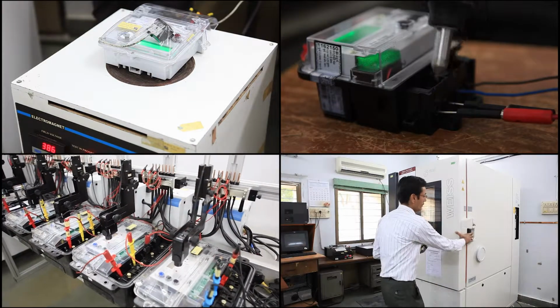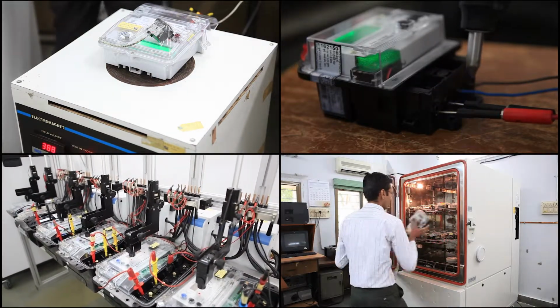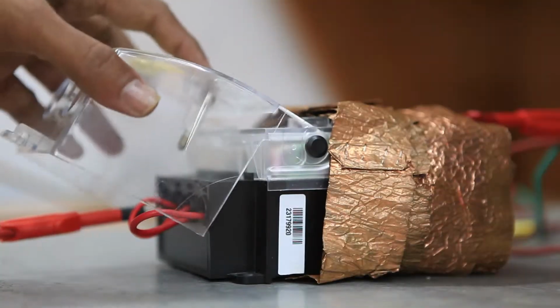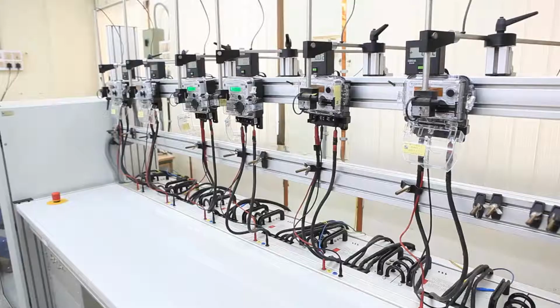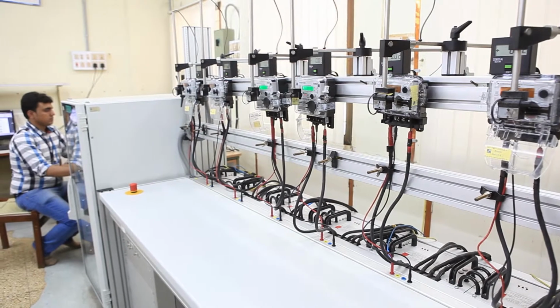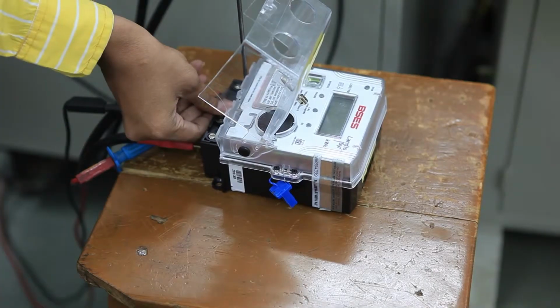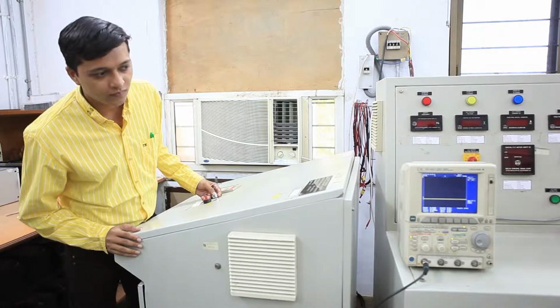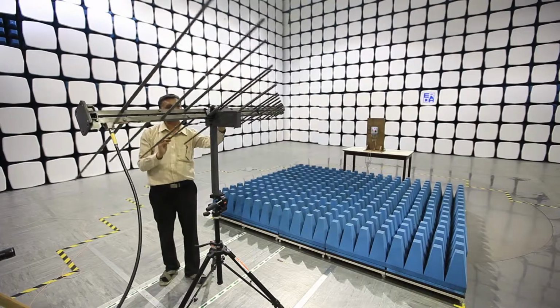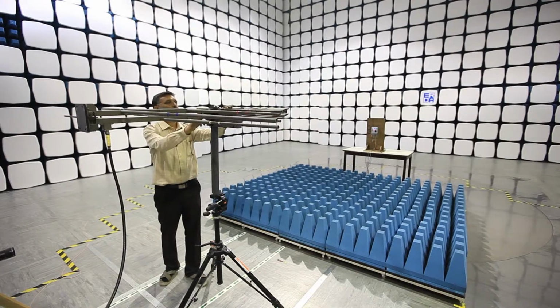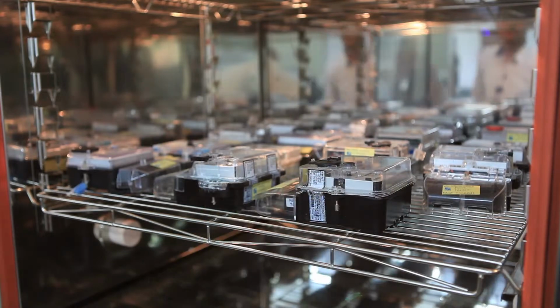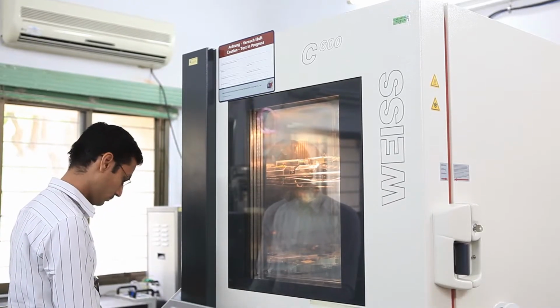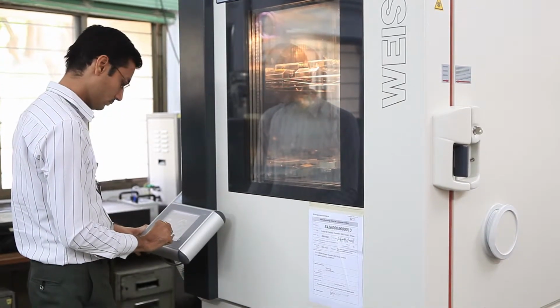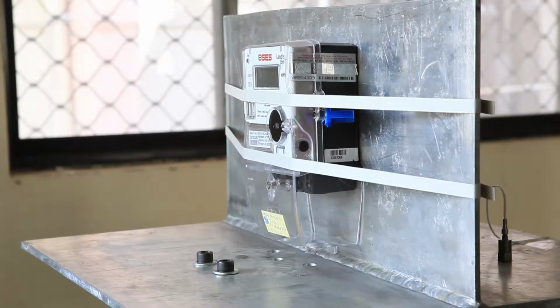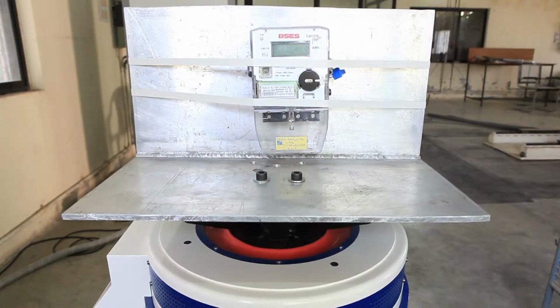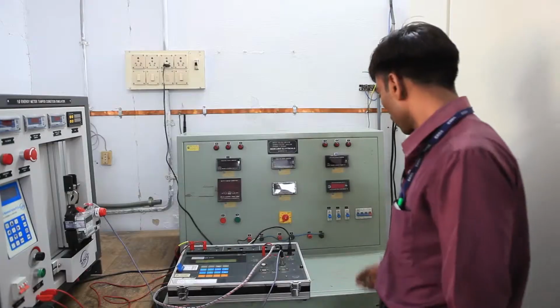ERDA has complete type test facilities for energy meters. We carry out impulse test, accuracy requirements up to 0.02 class, short time overcurrents up to 10 kiloamperes, and EMI EMC tests. 15 batches of energy meters are simultaneously tested in 3 fully automatic climatic chambers. We have facilities for vibration and shock test also.